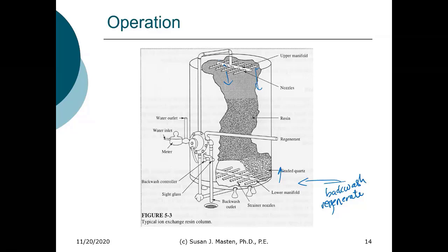Anybody catch that? So what was the problem? He said what the contamination was. He said that it was salt contamination. So what's happening? You're pumping the salt contaminated water back into the aquifer. Exactly. And altering its ion content. That's exactly what was happening. So they stopped doing it because, as they didn't have centralized softening, much of the community had water softeners in the home.